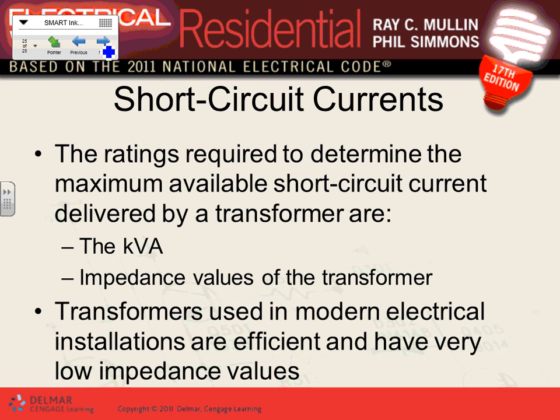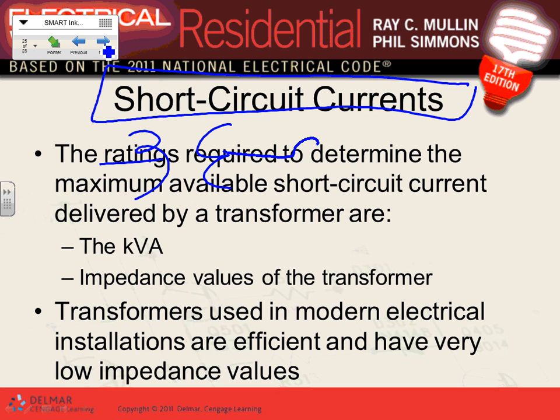Okay. So all these short circuit and all this mess that we're talking about, guys, fully rated and so forth, is coming from a short circuit. Short circuit rating starts with the transformer. I'm going to take a very, very simple example, guys, because that's very important. So here's a transformer. Suppose this transformer was 25 kVA, and the voltage is 240/120, and the impedance, everybody knows what the impedance is? Right? The impedance, the resistance inside the transformer, is 5%.